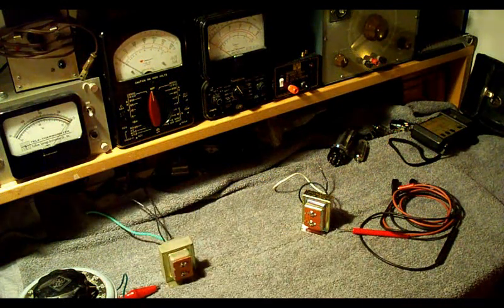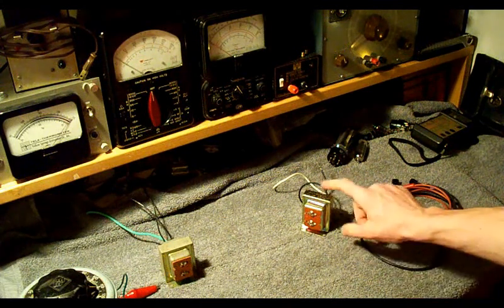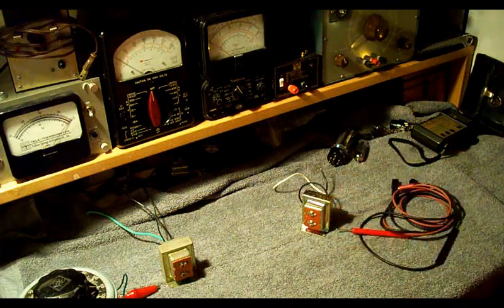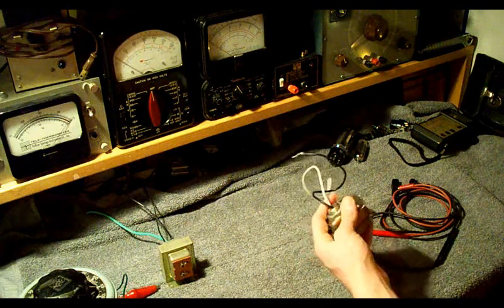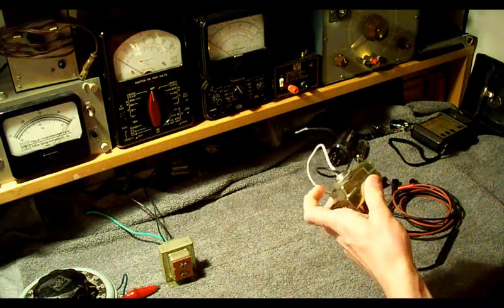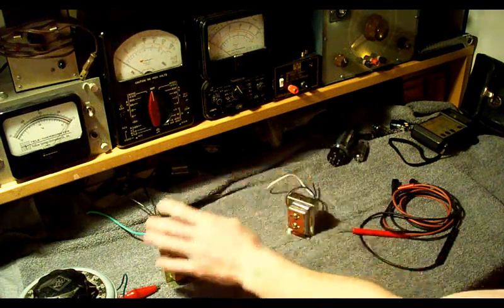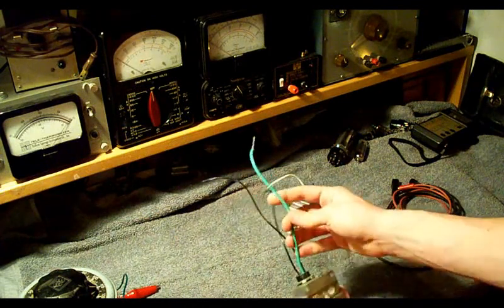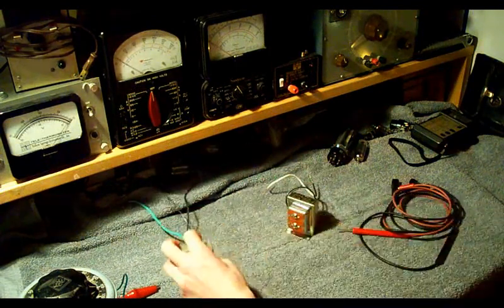Now you can test them two ways. One, you can apply an AC voltage to the transformer and measure the output. Or two, more importantly, you can check the windings with an ohm meter to check the resistance and also to check for any shorts to ground or leakage to the case of the transformer. And in this case, this one is not grounded, but it probably would be in the electrical box if it's mounted in one. But this one has an extra ground wire where you would connect it to your service ground.